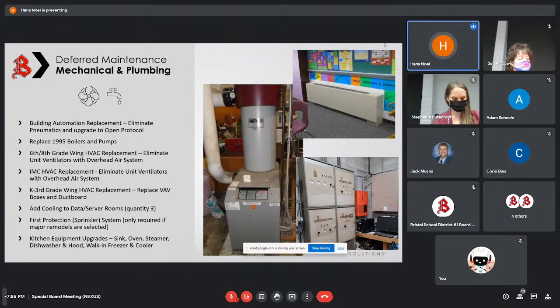MS14 is HVAC system optimization and retro commissioning. It's natural that controls are the heart of the building, and valves and dampers eventually go out of whack and need to be reset. We usually do retro commissioning every 5 to 10 years depending on the system. In this case, since we're replacing about half your control system, we want to do that, then go back and retro commission the controls that aren't part of the replacement, to make sure everything's working properly and we don't have areas cooling and heating at the same time. It's a thorough process - when we find equipment, thermostats, or temperature sensors that don't work, or sequences that aren't set up right, we get it corrected so the building operates most efficiently.